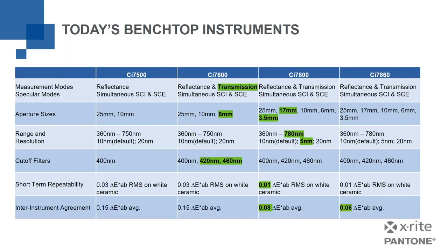And then finally, maybe one that's focused on a lot is inter-instrument agreement. Inter-instrument agreement means if I have two devices of the same model, how close will they agree with one another based on measuring something similar to BCRA tiles and calculating their color difference. And you can see that the 7500 and 7600 are at 0.15 average delta E. The 7800 is 0.08, which equals the best that had always been traditionally available on the previous instruments and from competitive devices. And the 7860, the thing that it stands out for is that inter-instrument agreement down to 0.06.